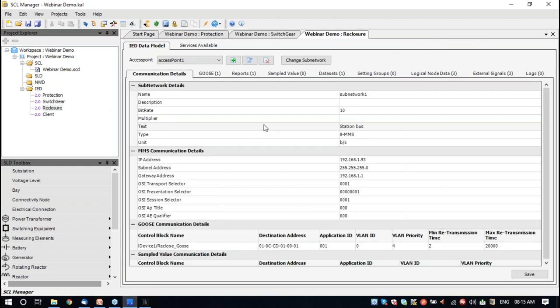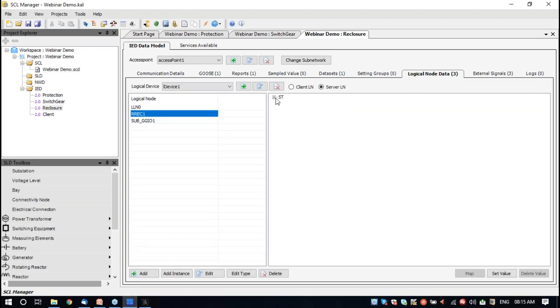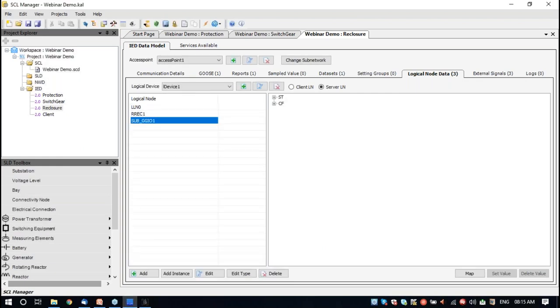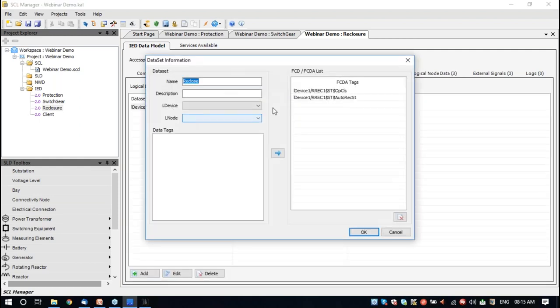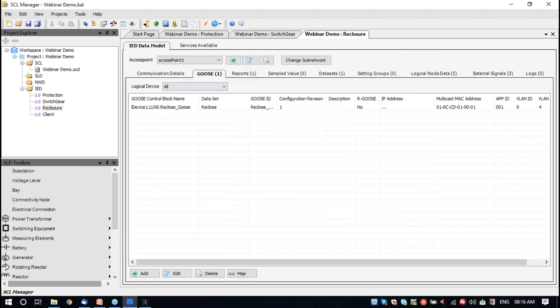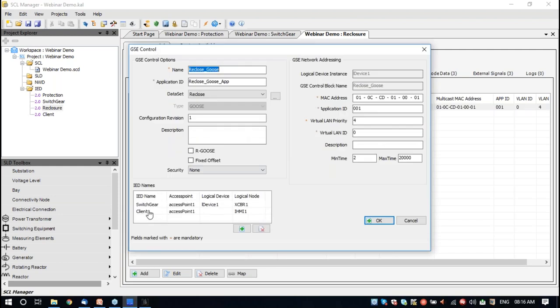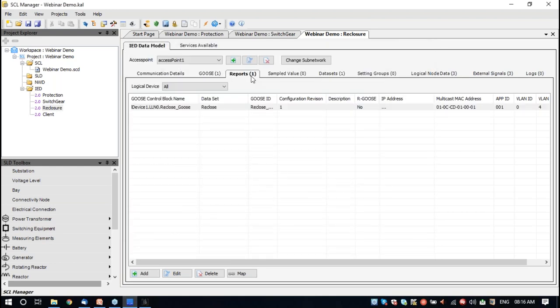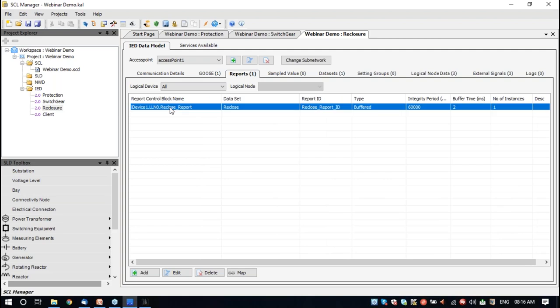We also have a recloser device. It has got a recloser logical node to send out the operation. There is also a subscriber GGIO to receive the circuit breaker status. The recloser device has operation close and auto-reclosure status. We have the GOOSE signals going out from the recloser to the switchgear and client, and finally the report going out from this device to the client.